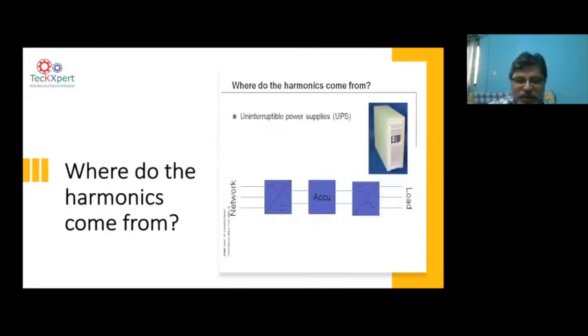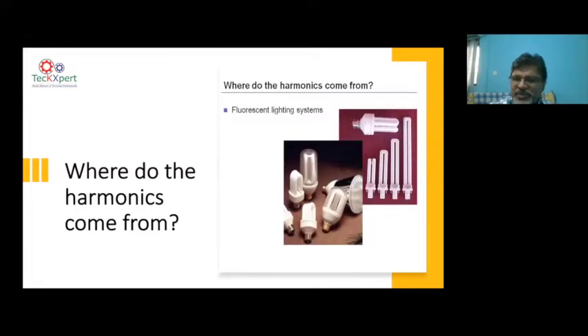UPS, everywhere, single phase and three phase, is again another culprit of harmonics, because here again we use the same principle of conversion, rectification and inversion. And the next one, of course, is CFL, which is your conventional tube light bent into a few small tubes and put into a holder. Fluorescent lighting, as you all know, uses magnetic or electronic ballast. Conventional tube lights are familiar with magnetic ballast. These electronic ballasts again have a rectifier circuit and an inverter circuit, because for this CFL or LED to burn at a constant current, you need to convert the voltage from AC to DC and then to the required AC. So there again it produces harmonics. And go into the next one.